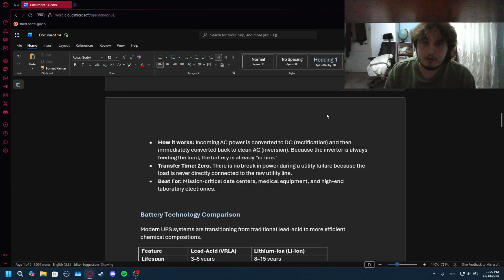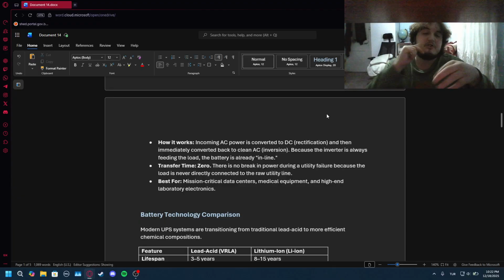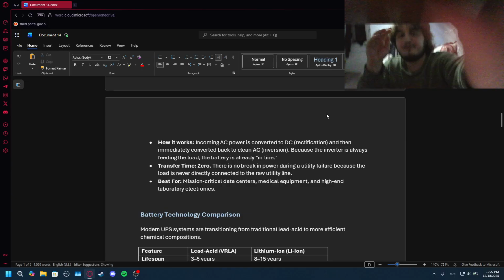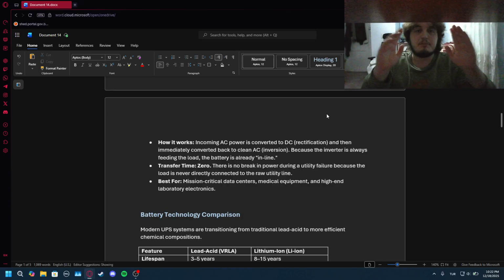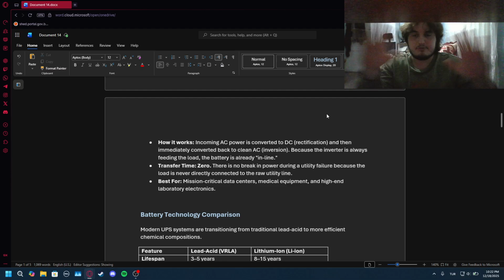So there's no break in power during a utility failure, because the load is never directly connected to the raw utility line; there are always two changes in between. You go AC, DC, AC, and in between that you have the battery always in line. So the light doesn't flicker like this. The power went out, you can still see me, and it's right there.